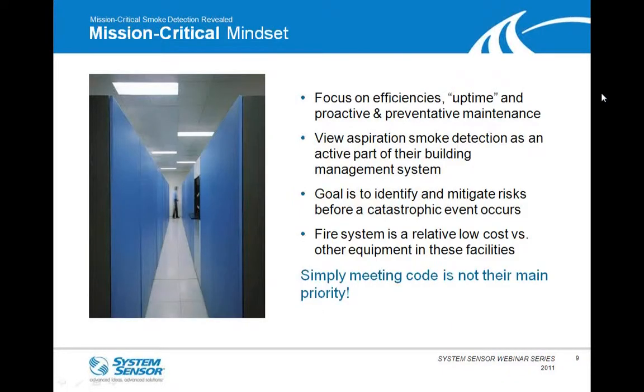As for the mission-critical mindset, I mentioned at the onset that the whole mindset and thought process is very different from what we're used to dealing with in smoke detection, where it's meet the minimum of the code, and that's all many people are looking for. Conversely, with mission-critical facilities, the focus is really on efficiencies, uptime, and proactive and preventative maintenance. Basically, anything they can do to keep things running without any interruption or hiccups. They view aspiration and smoke detection in general as an active part of their building management system. Rather than having a system where it alarms and you evacuate, they really want to use it as a means of managing that system, identifying the risks and mitigating them before they can turn into a catastrophic event.